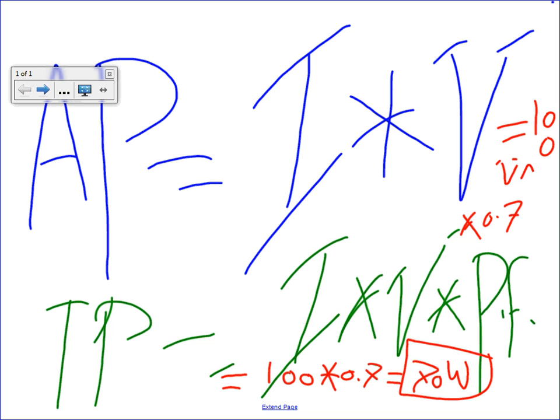This is volt amp. Take this, Rob, my friend. Xcel Energy is sizing their transmission line to give you 100 volt amp, and you single-handedly, because your building is screwed up with a power factor of 0.7, are only consuming 70 watt out of it. And what happened to the other 30 watt? Losses. And what happened to that big conductor coming to your building, sized for 100, sitting there? It's not utilizing it. So that's a big deal, guys.